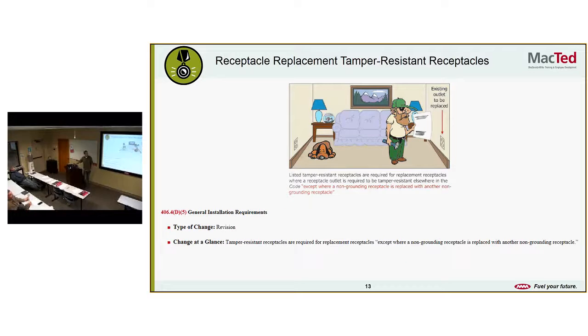Oh, this is a big one. If you're replacing receptacles in and around your house now, they want everything to be tamper resistant. So now they're saying tamper resistant receptacles are required for replacement receptacles except where a non-grounding receptacle is replaced with another non-grounding receptacle. So if you replace a two hole with a 2 hole, it doesn't have to be tamper resistant. But if you replace a 3 hole with a 3 hole or a 2 hole with a 3 hole, it has to be tamper resistant. So any outlet you replace nowadays, you gotta use a tamper-resistant one, because kids don't have common sense or something. Except where a non-grounding receptacle is replaced with another non-grounding receptacle. It's hard to find a non-TR receptacle.